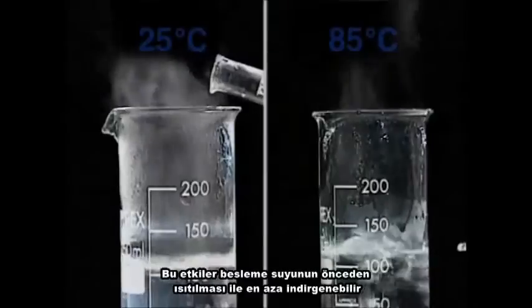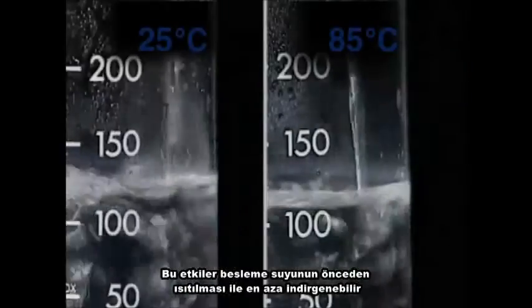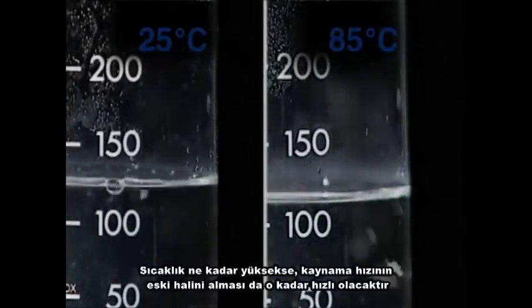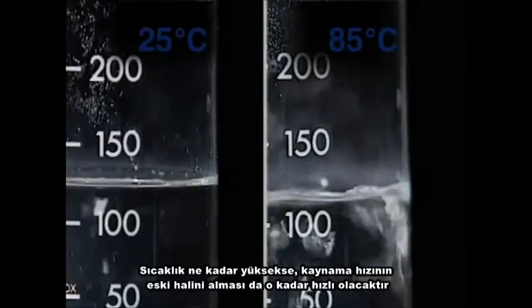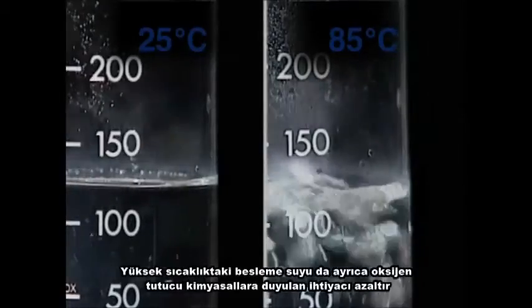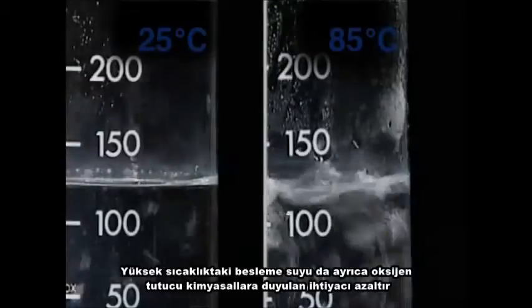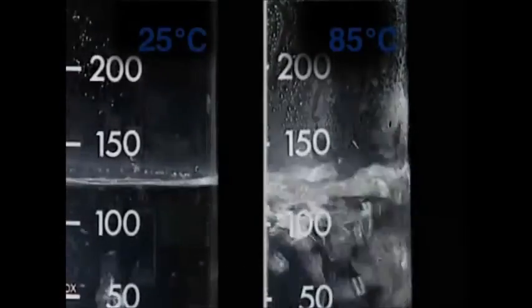So with on-off control, not only does the water level continue to rise and fall, but so too does the steam output rate. These effects can be reduced by preheating the feed water. The higher the temperature, the quicker the boiling rate can recover. Higher temperature feed water also reduces the need for oxygen scavenging chemicals.